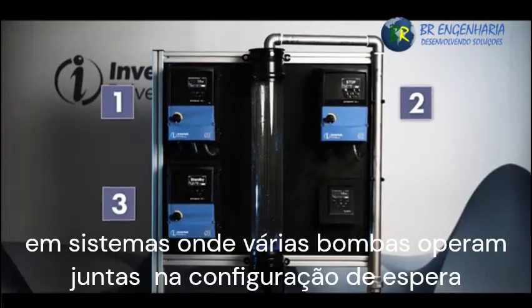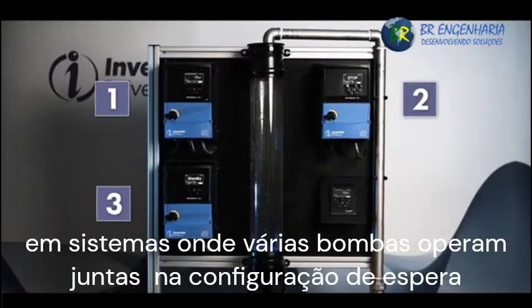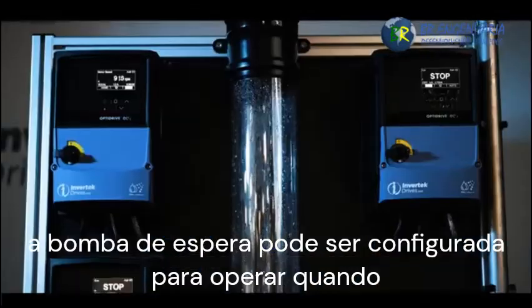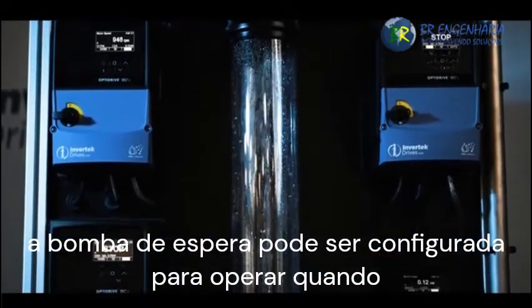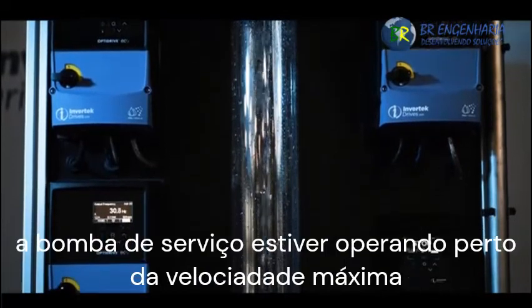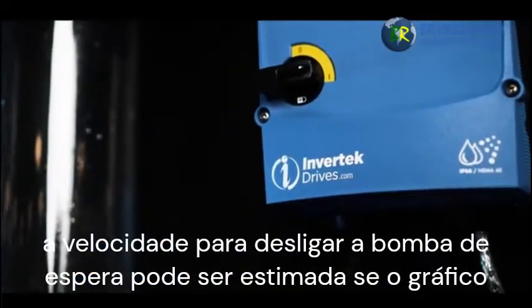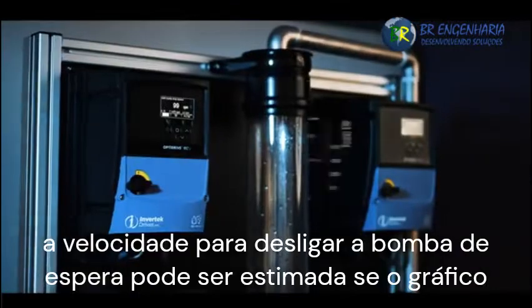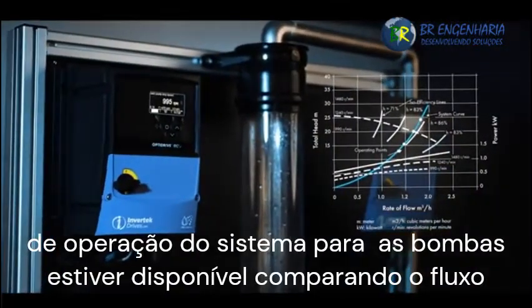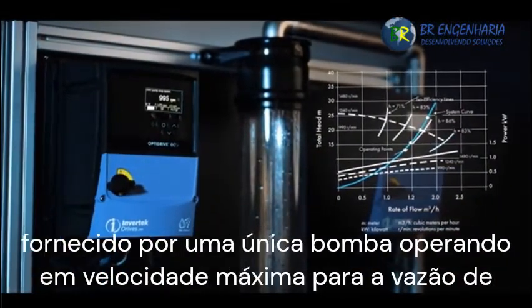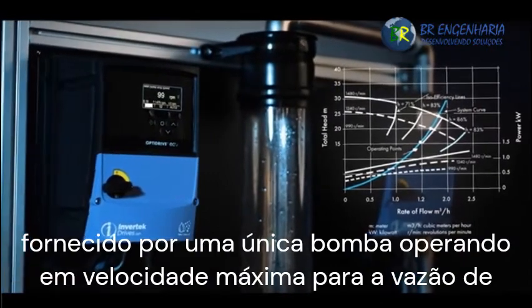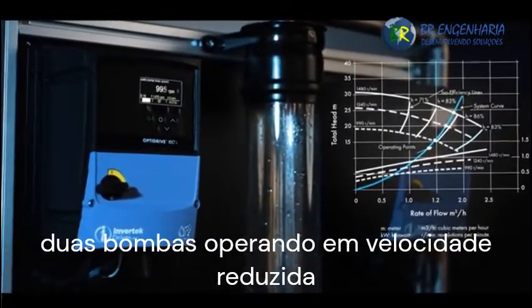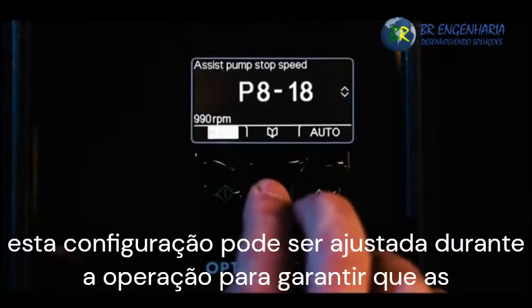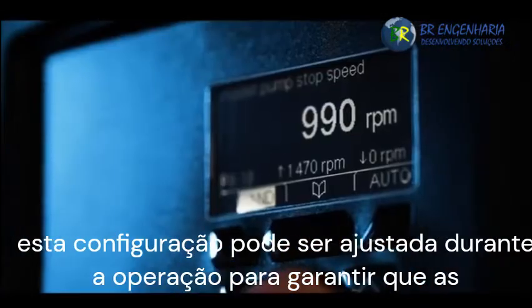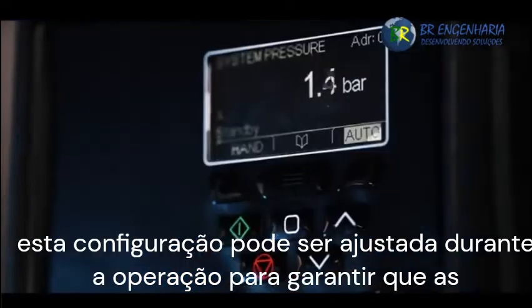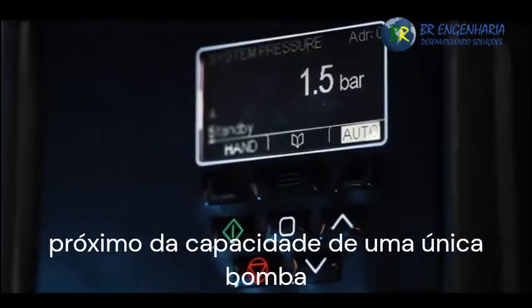In systems where multiple pumps operate together in duty assist standby configuration, the assist pump can be configured to start when the duty pump is operating close to maximum speed. The speed to switch off the assist pump can be estimated if the system operating graph for the pumps is available by comparing the flow provided by a single pump operating at maximum speed to the flow of 2 pumps operating at reduced speed. This setting can be fine-tuned during operation to ensure that the pumps do not repeatedly start and stop when the flow is close to the capacity of a single pump.